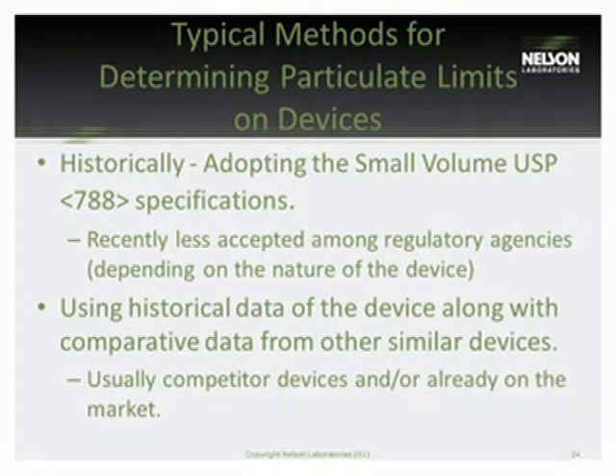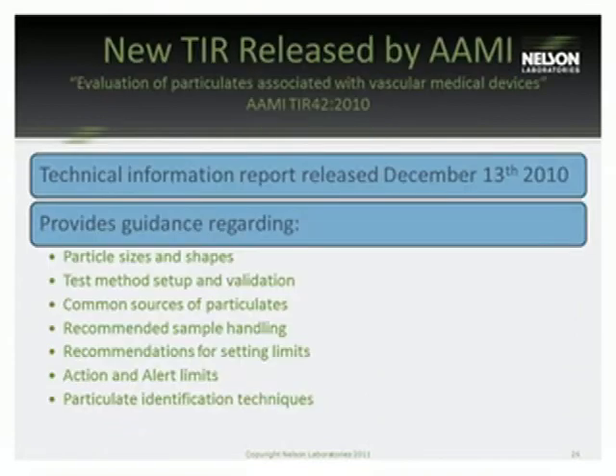And the justification for this is probably fairly straightforward. That is that if a device or product is on the market and is shown to be relatively safe clinically and contains the same or more, or at least similar amounts of particulate matter to the device that's being tested, then it can be justified that it should be relatively safe. It is helpful to have other tests combined with these when using these methods of comparison. Endotoxin testing, TOC, total organic carbon, tests like that can show biocompatibility and are also good when using a comparative method, as particulate matter is just one of several tests, as you know, that have to be conducted on a medical device.